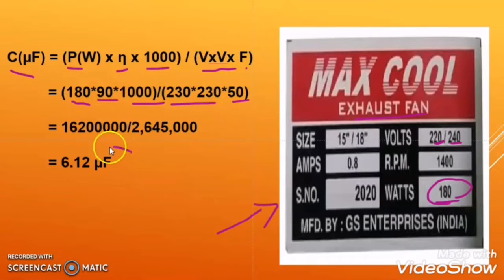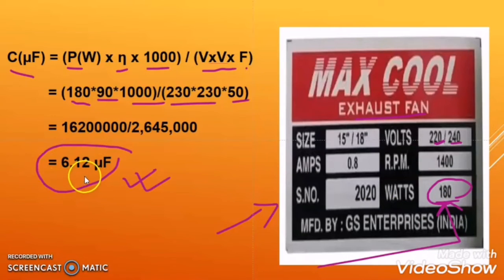So I put efficiency as 90, 1000 is a constant, divided by the single phase voltage. The voltage is given as 220 or 240, so I took the value in between, which is 230, and the frequency in India is 50 Hz. When I calculate, I get a value of 6.12 microfarad. So for this 180-watt induction motor, we need a capacitor of 6.12 microfarad.